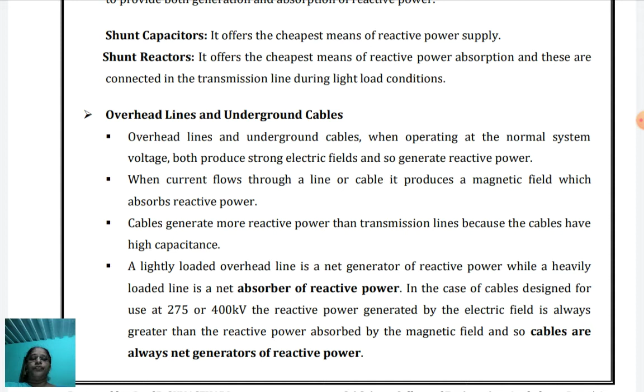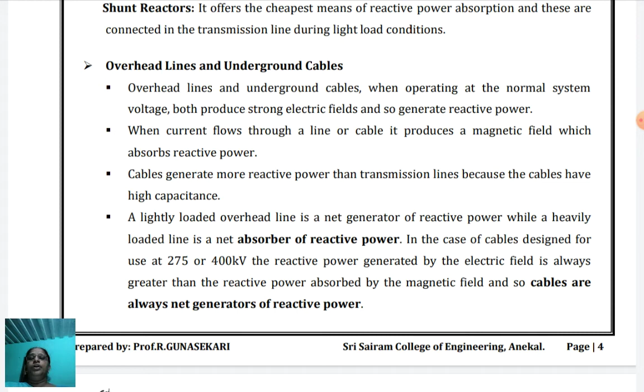A lightly loaded overhead line is a net generator of reactive power, but a heavily loaded overhead line is a net absorber of reactive power only. The reactive power generated by the electric field is always greater than the reactive power absorbed by the magnetic field. Therefore, cables are always net generators of reactive power only. Transmission lines are considered as generating kVAr in their shunt capacitance and consuming kVAr in their series inductance only. You see the diagram.